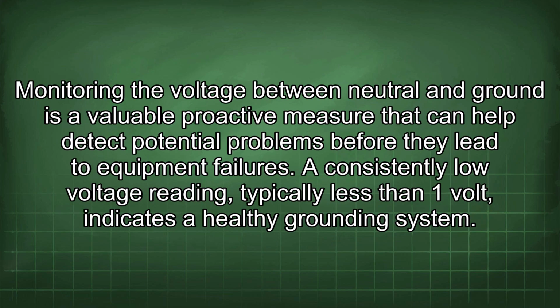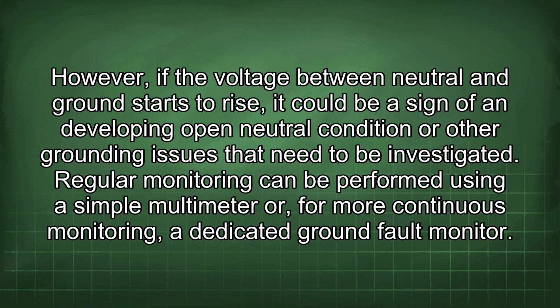250.66. Monitoring the voltage between neutral and ground is a valuable proactive measure that can help detect potential problems before they lead to equipment failures. A consistently low voltage reading, typically less than 1 volt, indicates a healthy grounding system. However, if the voltage between neutral and ground starts to rise, it could be a sign of a developing open neutral condition or other grounding issues that need to be investigated. Regular monitoring can be performed using a simple multimeter or, for more continuous monitoring, a dedicated ground fault monitor.